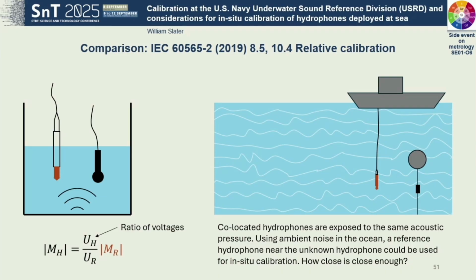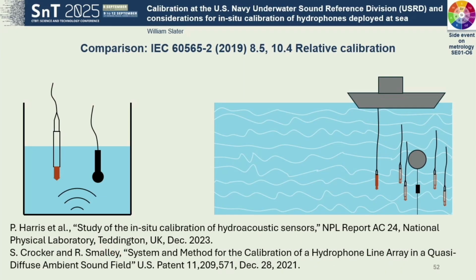In an exploratory study, Harris et al. from the National Physical Lab in the UK showed that an ambient side-by-side method can work, but with degradation in the uncertainty of the calibration for separation distances of even just a few meters. This degradation can be monitored using the coherence of the signal from the hydrophones. But again, the coherence was adequate only at the lowest frequencies.